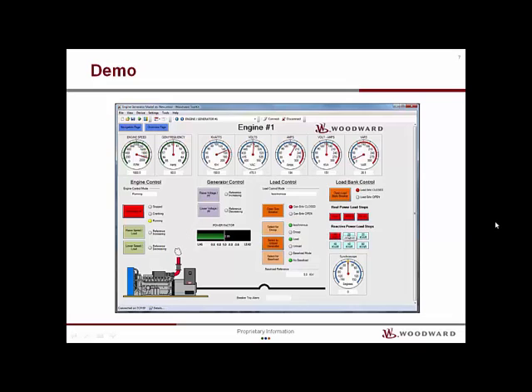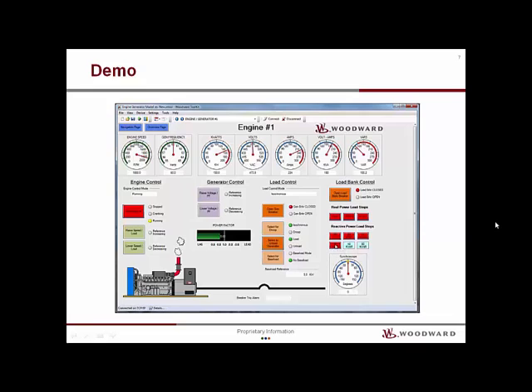I will add some reactive, inductive power. Notice that as the reactive load is added, the kW don't change, but the current on the generator increases and the power factor decreases. The reactive power is removed, the real power is removed, and the generator breaker is opened.